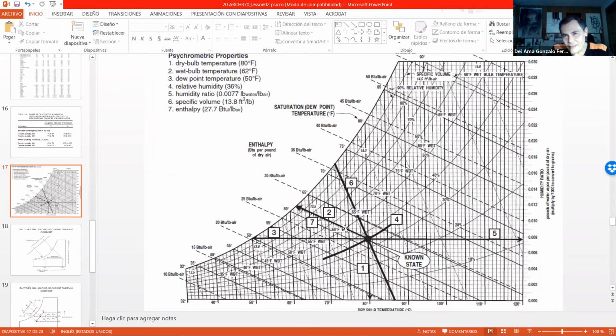In this point, if we move, this is 7 - it's the same line I used to calculate the wet bulb temperature, but this is the enthalpy. The enthalpy lines are all these dashed lines we have here, measured in BTU per pound of air.